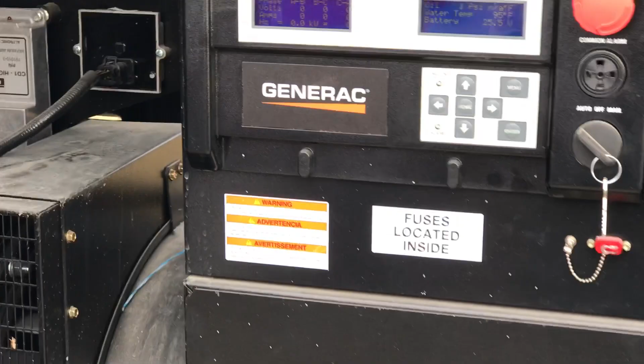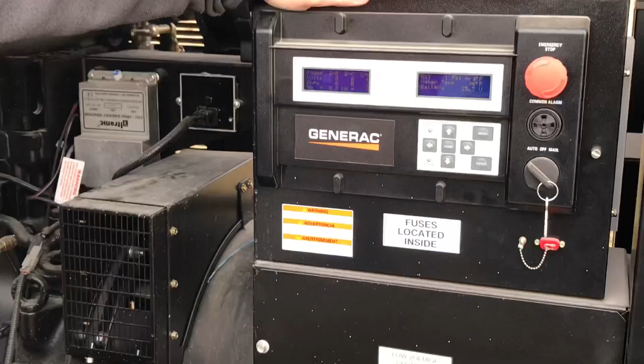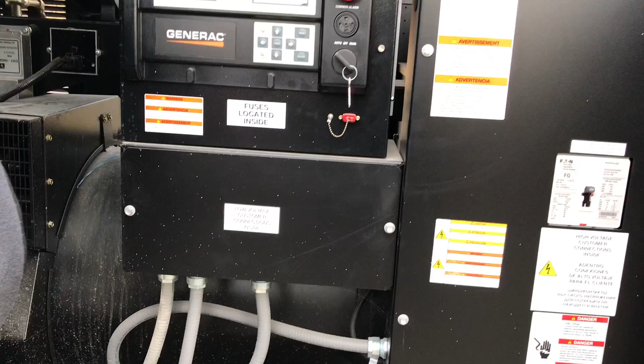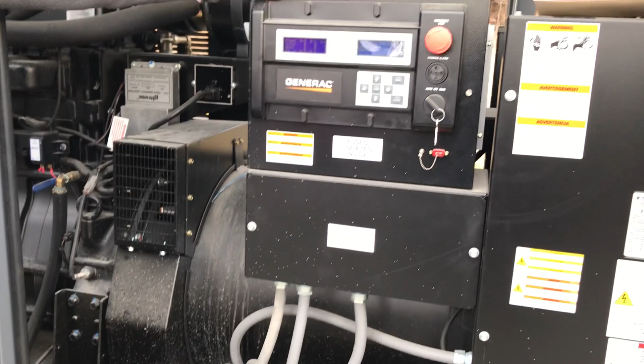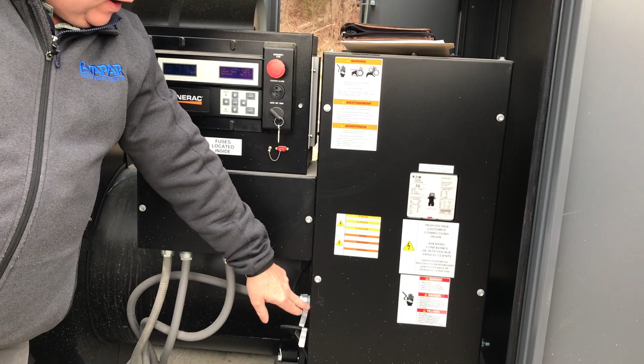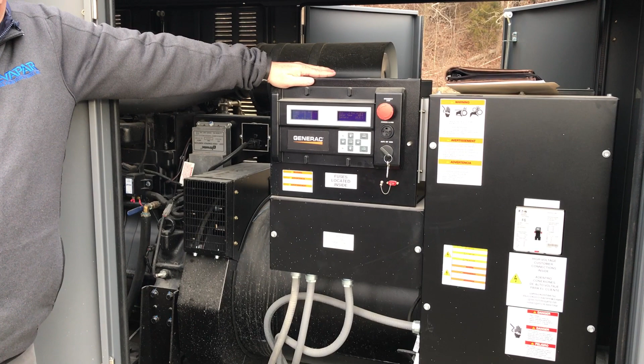As you can see down here, this is the block heater system, and it's actually plugged in to a GFI. So if you open this door and you see low coolant temperature, it actually happens a lot. For some reason, that GFI trips. Just reset it. Usually okay. This unit does not have a load center. You know where the circuit is that came out here? Okay, all right. So there's one circuit that came out here that's feeding a terminal block right here that's feeding the block heater, the battery charger, and those kinds of circuits in the system. So if it does trip and you got something wrong, there's no power, you need to find that breaker, make sure inside the building it hasn't tripped.